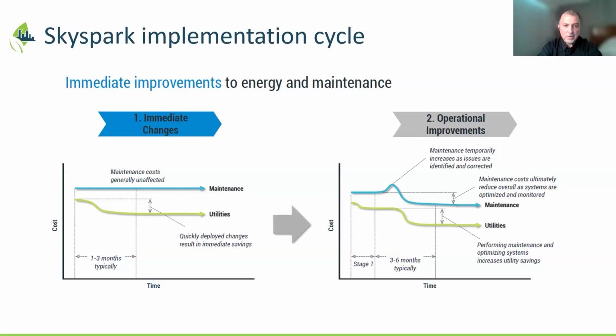The immediate expectation should be a reduction in utility bills because you're identifying the low-hanging fruit for energy saving. For example, are the schedules all set up appropriately? Early on, we found a fantastic BAS system where all the schedules were set up, but through no fault of any operator, an adjustment was made and the schedules changed, so air handlers were starting when there was nobody in the space. That happens, and nobody would know unless you had an overlaying supervisory fault detection system to point it out.